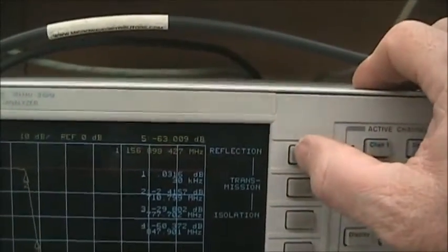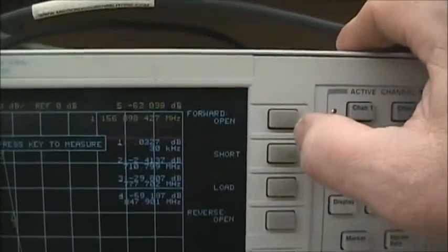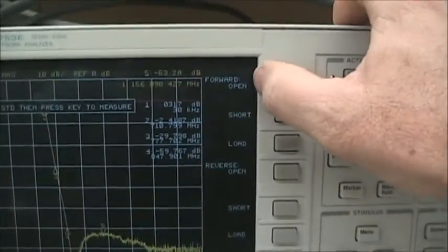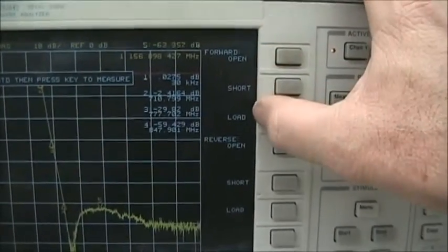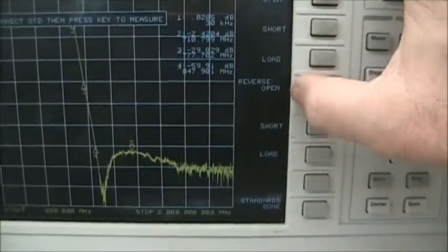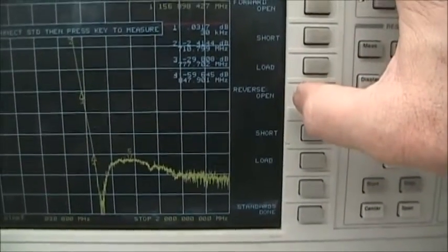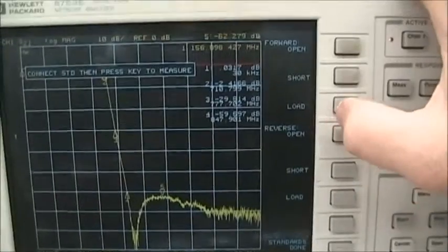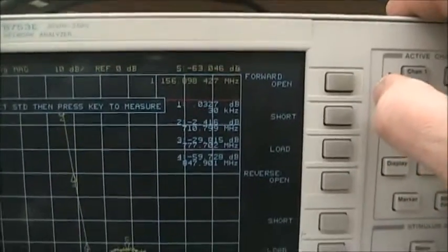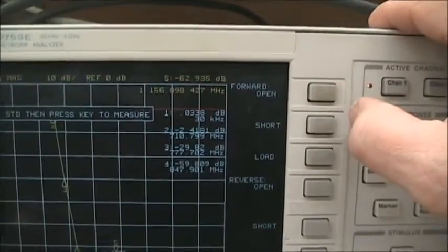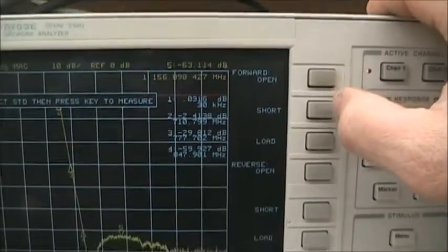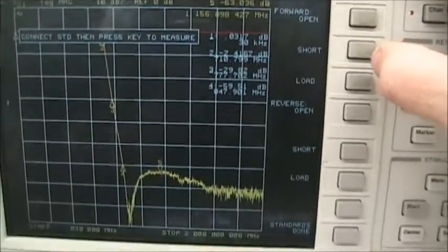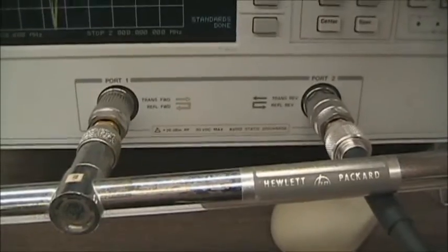I press reflection, and I see that I have open short load SOL for the forward port, port one, and SOL open short load for the reverse port, port two. These are the similar calibration standards we used on the original one-port calibration. Now we need to disconnect the filter and put on the load.